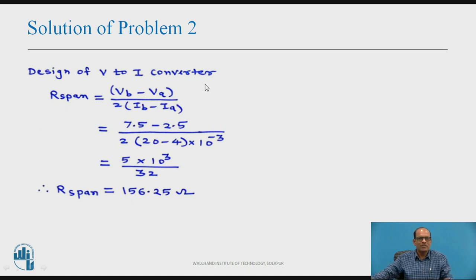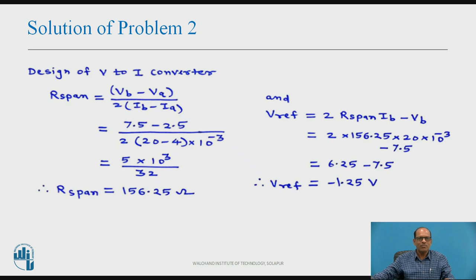Design of V-to-I converter: R-span is given by (V-B minus V-A) divided by 2 × (I-B minus I-A). Substituting values — (7.5 minus 2.5) divided by 2 × (20 minus 4) × 10⁻³ — this comes to 156.25 ohm. V-reference is given by 2 × R-span × I-B minus V-B. Substituting: R-span is 156.25 ohm, I-B is 20 mA, and V-B is 7.5 V. Therefore, V-reference equals minus 1.25 V.